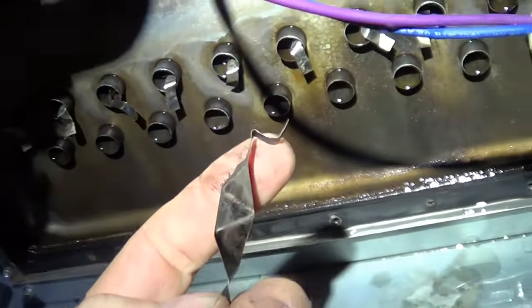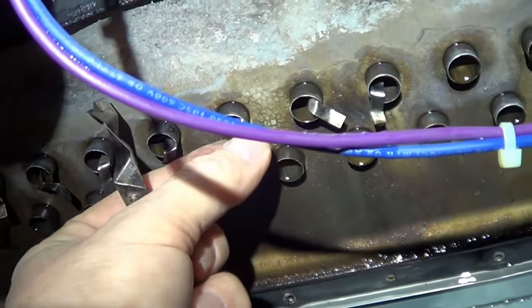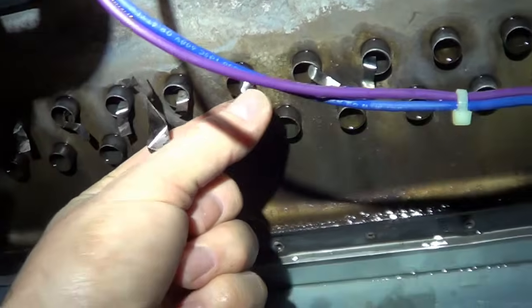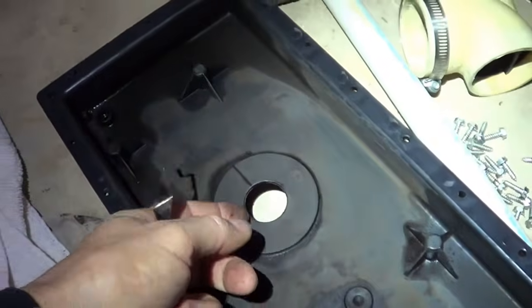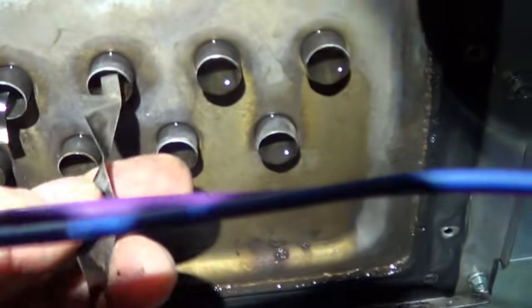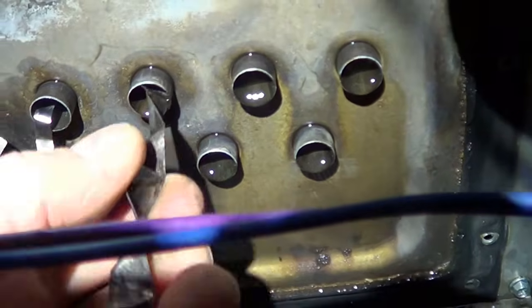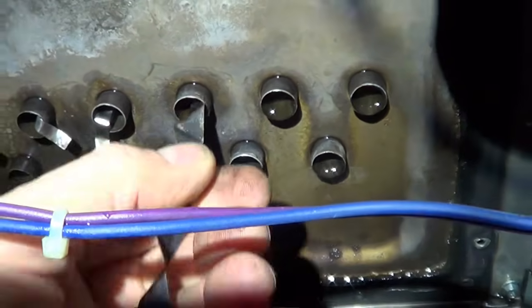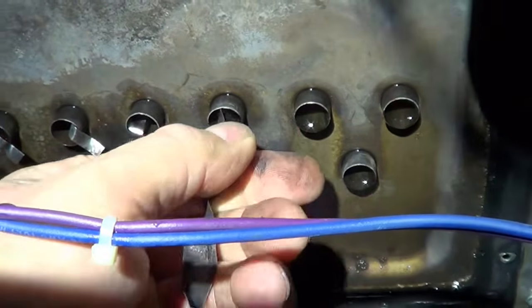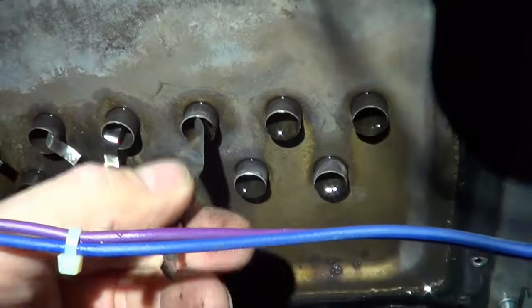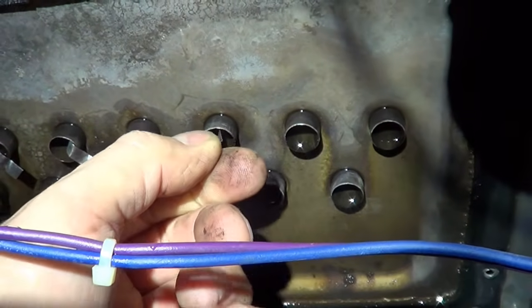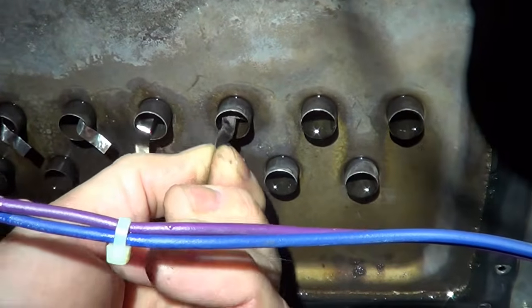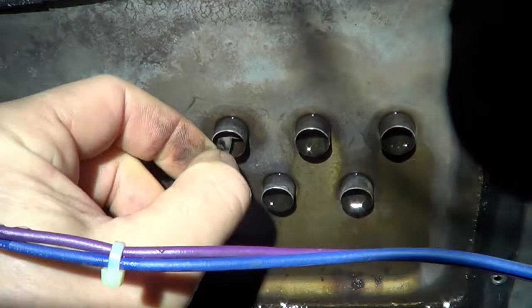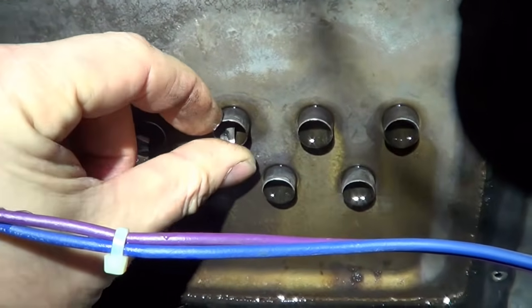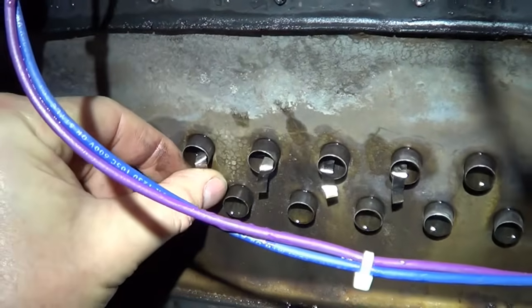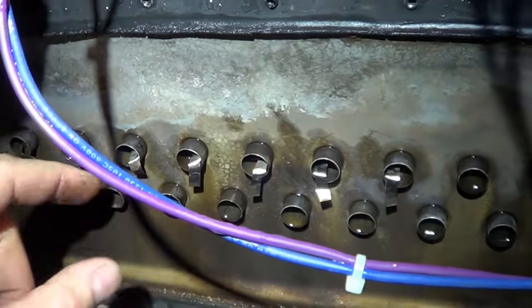I want to show when they slide back in, this tab, you want to have it grab the end of the pipe on the back side, because you don't want these coming forward and then getting sucked into the fan and then causing the fan to shut down. So it slides in just like so. Has a little bit of friction, but it does slide. And Goodman stuff's pretty easy to work on. And then once it grabs the back, you'll feel it. Yeah, hear that click, and feel how it's grabbing, so it doesn't want to slide forward. And when I pulled these out, I just twisted them and pulled to get them out, and then bend the tab. And bending the tab down is good. That way the water can drip downwards on these tabs.